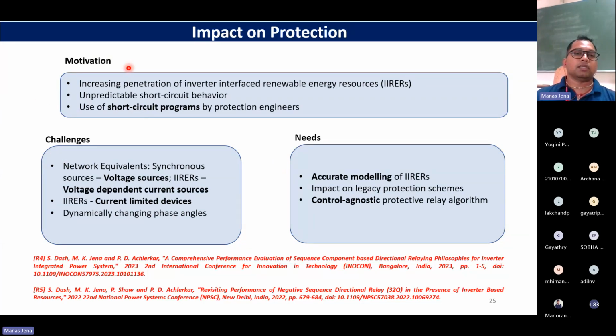So, motivation: increasing penetration of IBRs and unpredictable short circuit behavior. Those who work with power electronic converters will know that a current limiter is put in the control circuit because they want to safeguard the switches of the converters. So inverter-based resources are not expected to provide a fault current beyond 1.1 to 1.2 per unit following a short circuit, whereas in the conventional case we used to see fault current as high as 5 per unit, 10 per unit for synchronous machine based resources during fault scenarios.